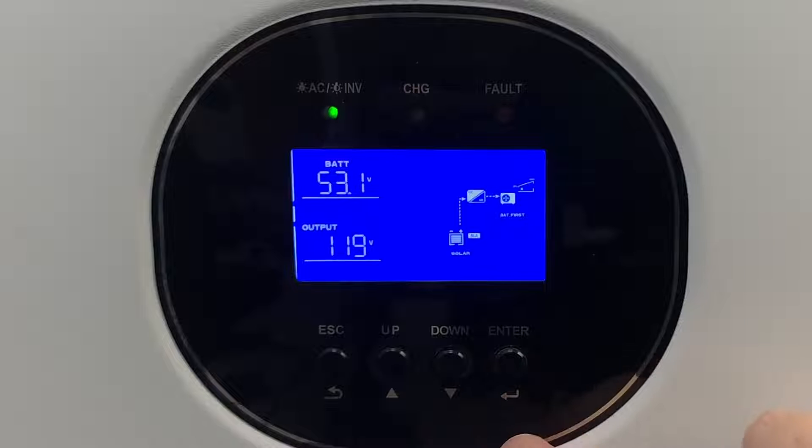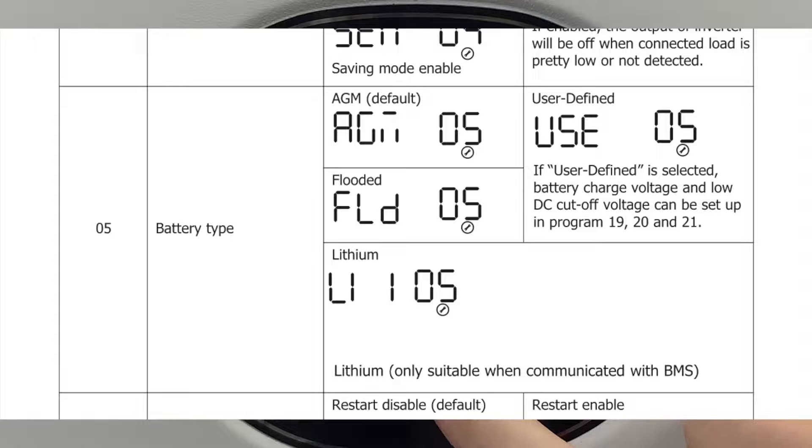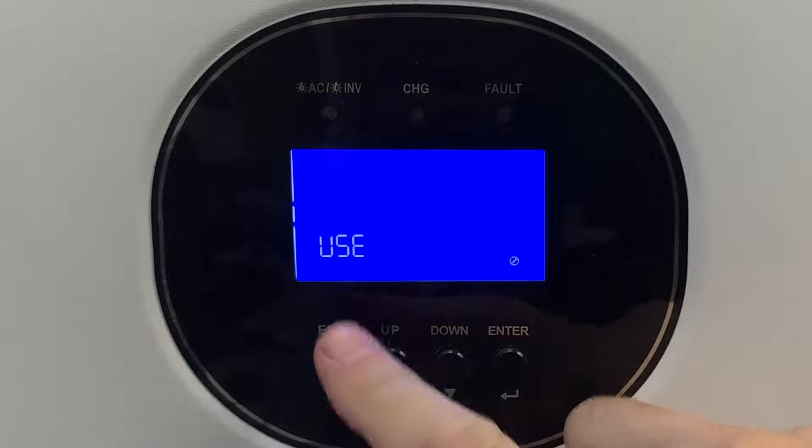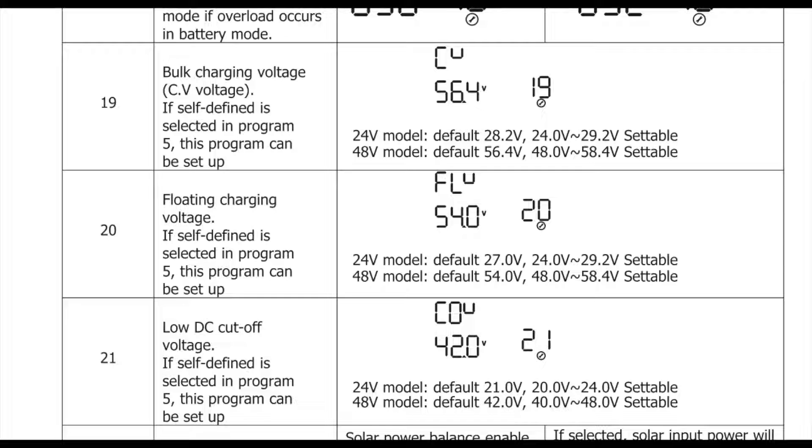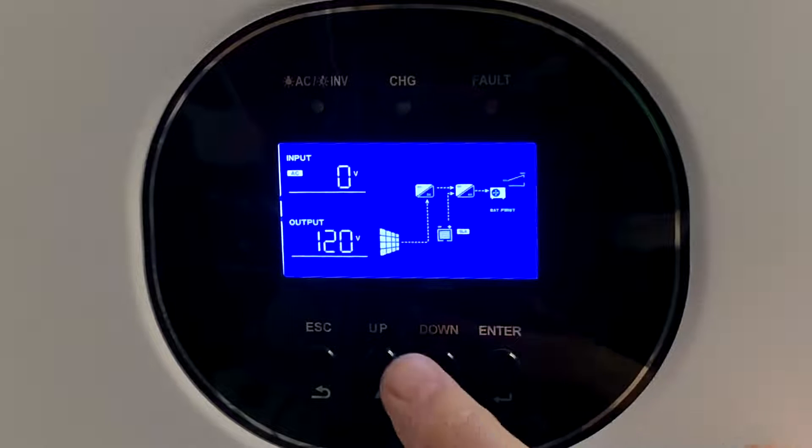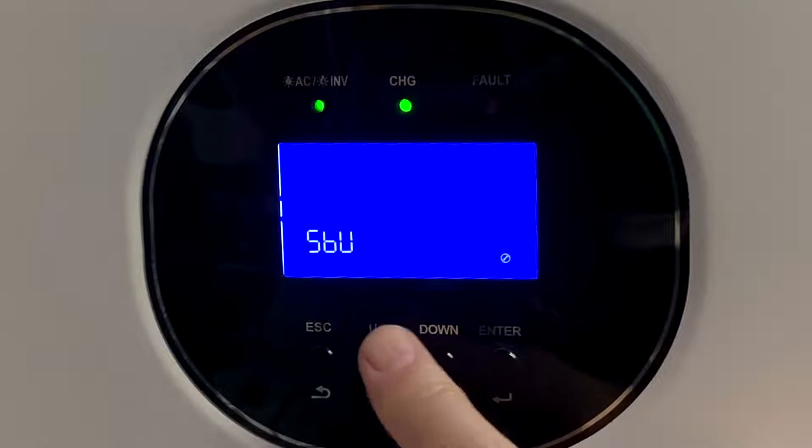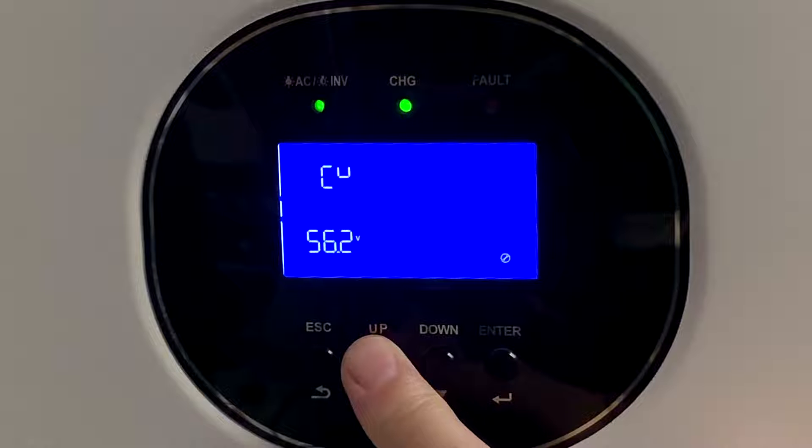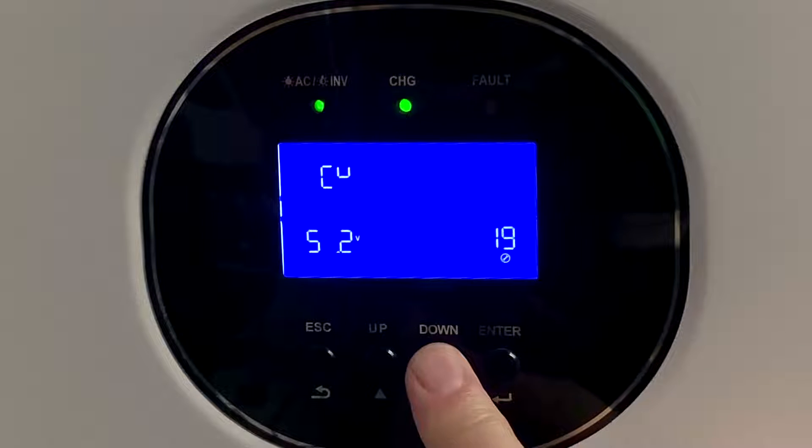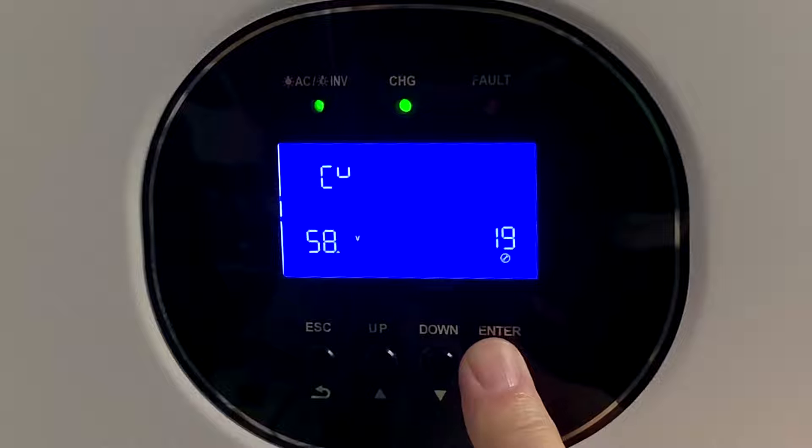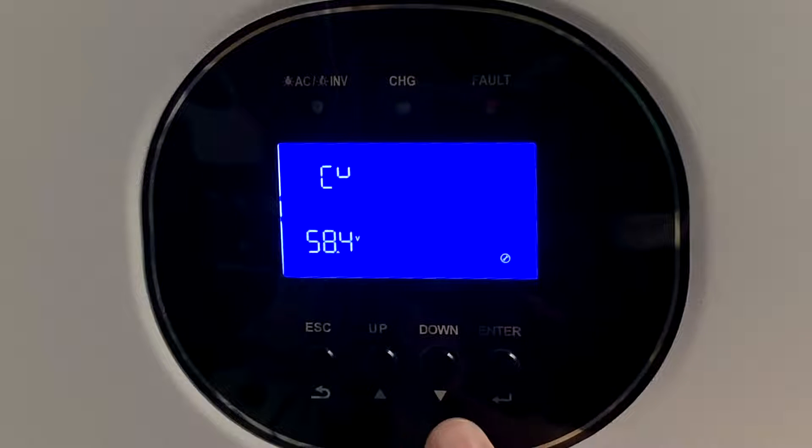So we have to be able to charge by voltages and not by percentages. So, in the GrowWatt, I have to go to setting number five and change that to user mode, and that allows me to set the charging voltage. And the charging voltage is set under setting number 19. It's bulk charging voltage. It could also be absorption voltage on some chargers. So, we're going to go in, and I'm actually going to go from the end of the menu backwards because it's faster to do it that way. And here we are on setting number 19. So, instead of it being 56.2, we're just going to jump it up and change this to 58.4. And store that.